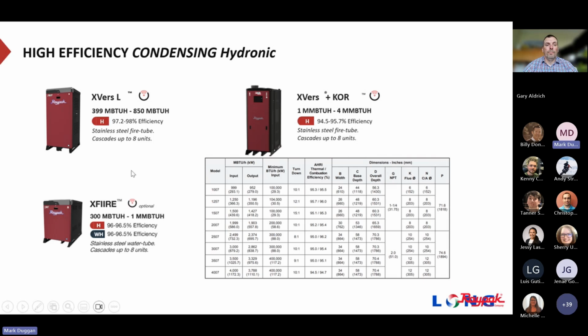We also offer our X-Fire unit, which is 300,000 to 1 million BTUs. This is a Sermeta water tube heat exchanger, so that burner sits inside of the heat exchanger and the water circulates around it. The nice thing about that Sermeta heat exchanger is it can be used for hydronic heating or water heating. Again, it comes with the Versa control. You could get it with dynamic protection as well as an adder. And just a nice option if you're needing space heating or water heating. So that's our condensing equipment.